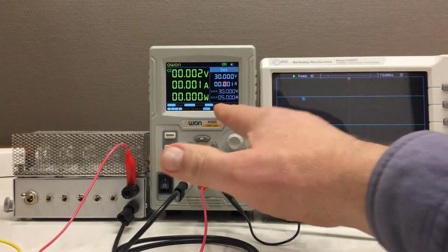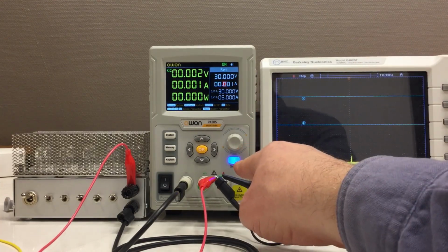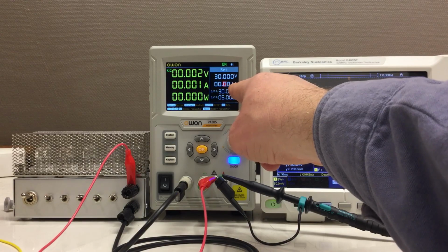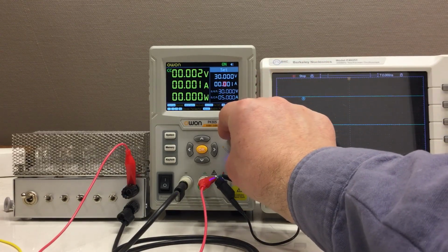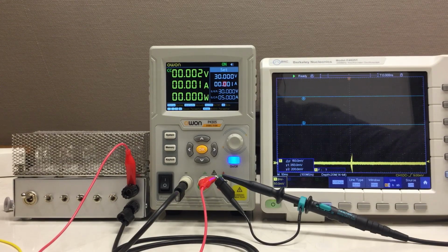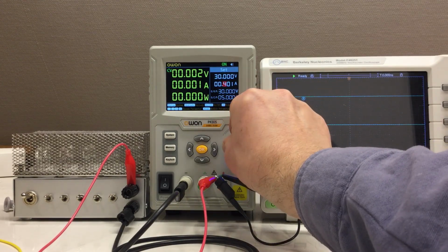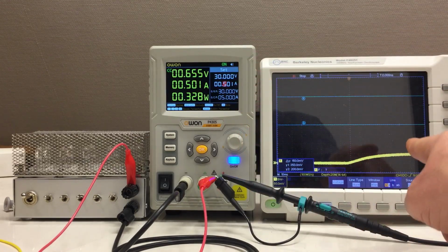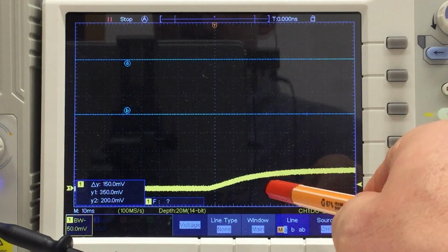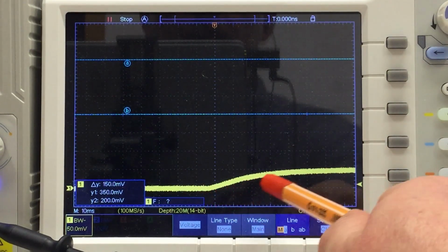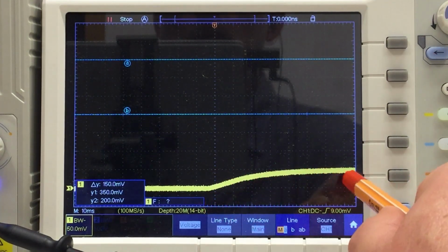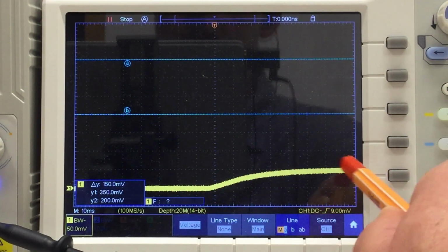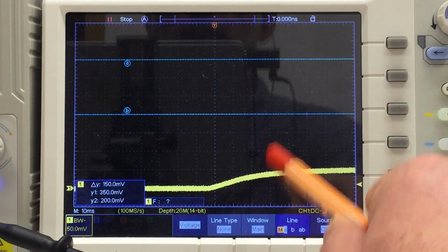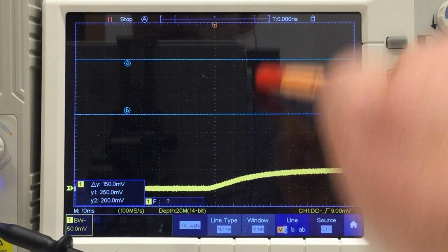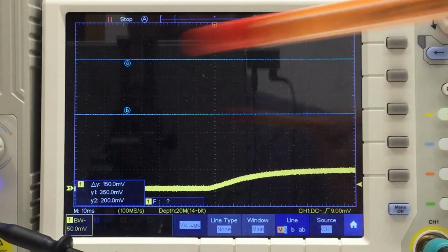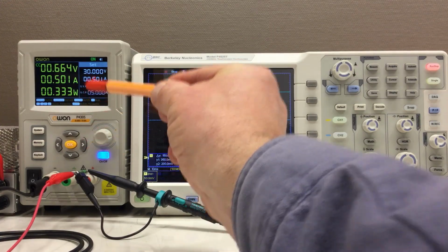No. Let's try that a little bit differently. The output is on, but I'm at a current limit of 1 milliamp. And now I will turn that up to 500 milliamp. I have to go to single capture here. So 1, 2, 3, 4, 5. And oh, that looks much better. Same scale as before, but now it takes 50 milliseconds to ramp up. And nice ramp up, absolutely smooth, no overshoot. So that's the way to go. Do not use the output on off with constant current mode.